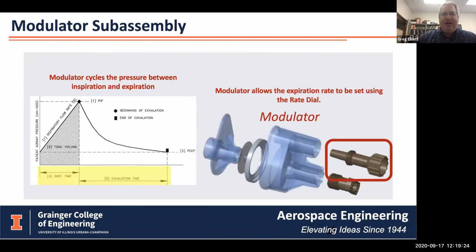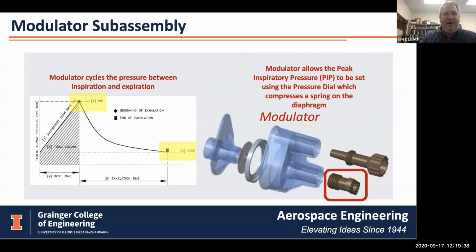And then the modulator. What it does is two things. It allows you to set the breathing cycle time, so the inspiration time and the exhalation time, through the rate dial. And it also allows you to control the PIP and PEEP pressures, through the spring-loaded...